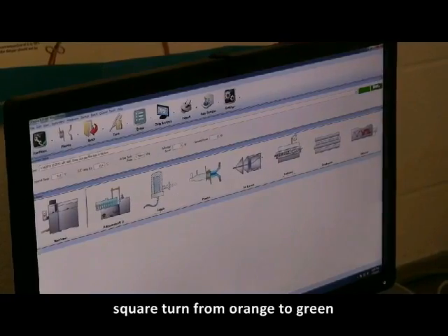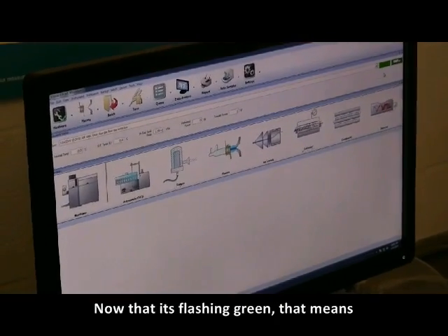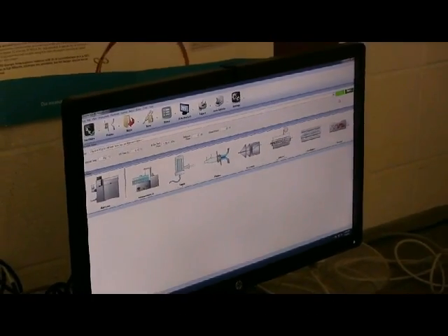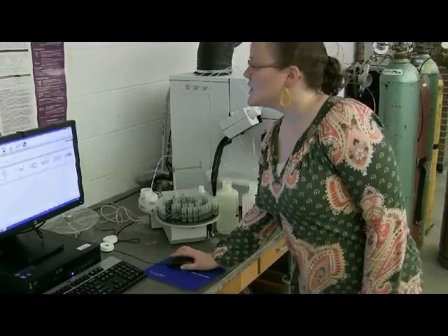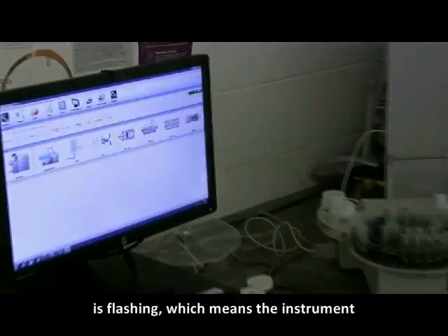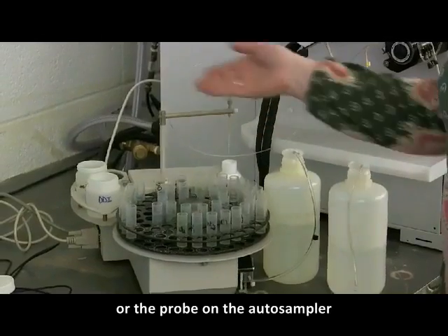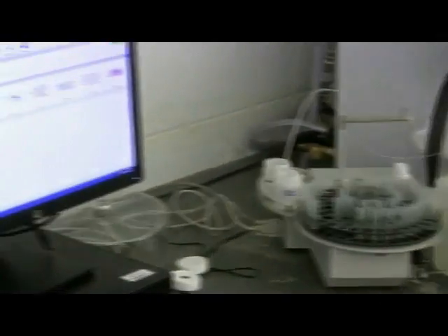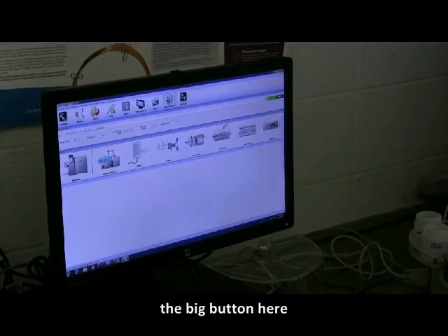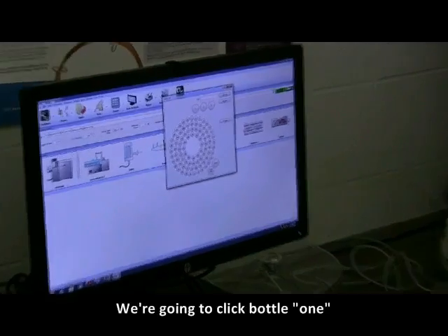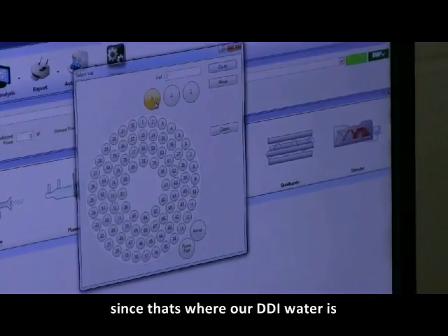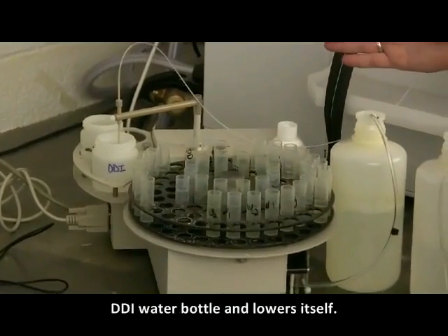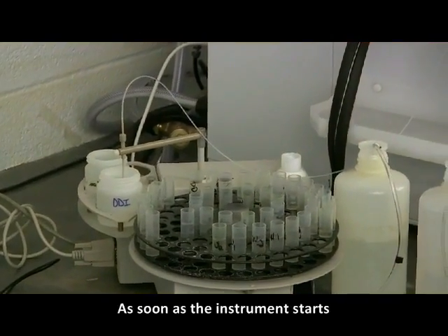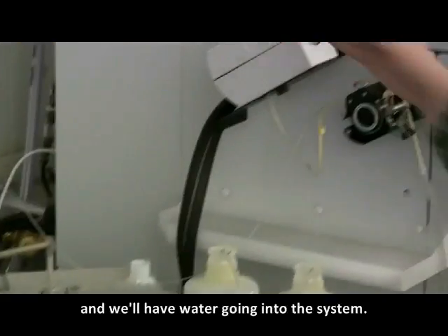You'll see that this square turned from orange to green. Now that it's flashing green, that means the instrument is preparing to turn on. After you notice that, we need to make sure that the needle or the probe on the autosampler is put into DDI water. So we click on autosampler, the big button here, and you'll see this looks like the autosampler. We're going to click bottle 1, since that's where our DDI water is, and then click go to. The probe moves to the DDI water bottle and lowers itself. As soon as the instrument starts, the peri pump will start turning, so we'll have water going into the system.